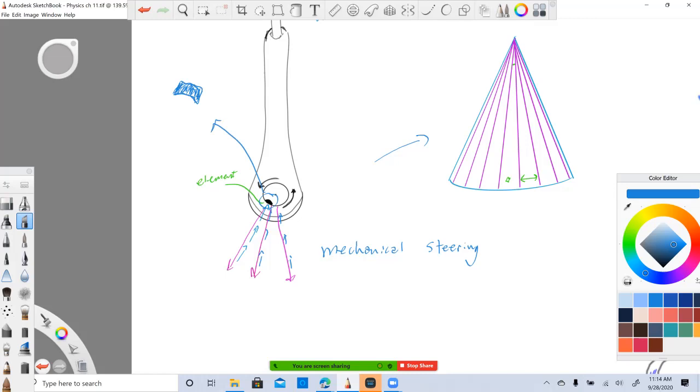That concavity is going to force sound together, and it's going to bring that focus up. So if the natural focus isn't where you want it to be, you can bring it closer, but you can't make it farther. You'd have to change the entire design of the element itself to make it farther. But if you want to bring it up closer, you make it a little bit concave.